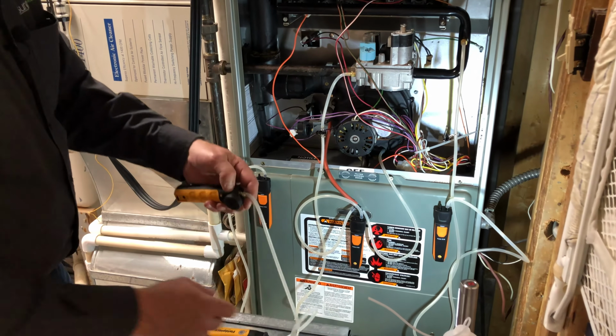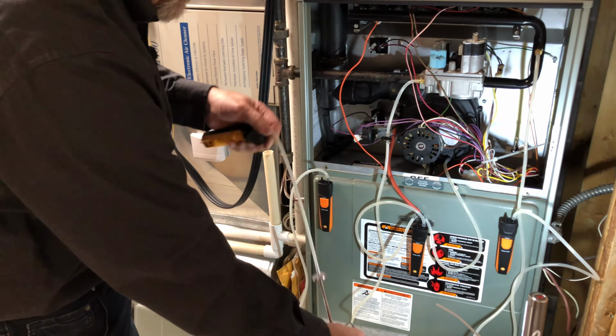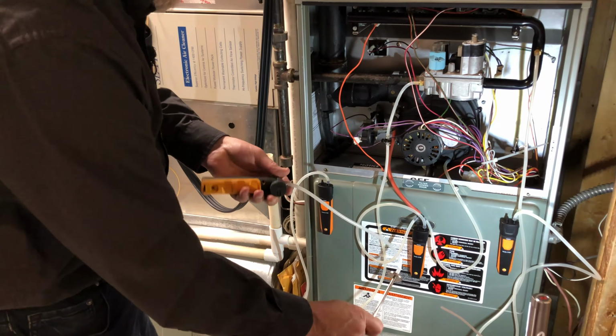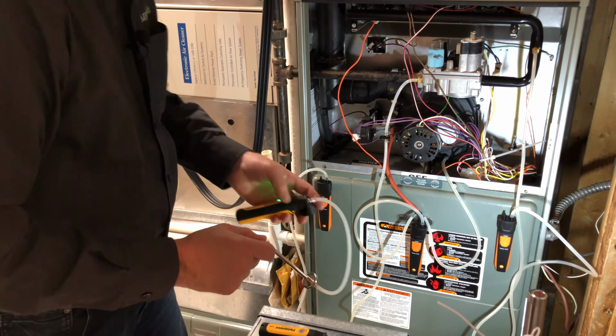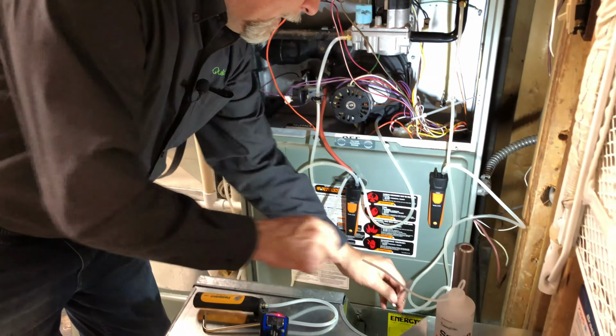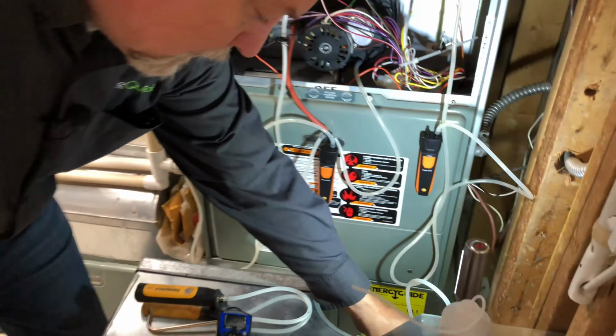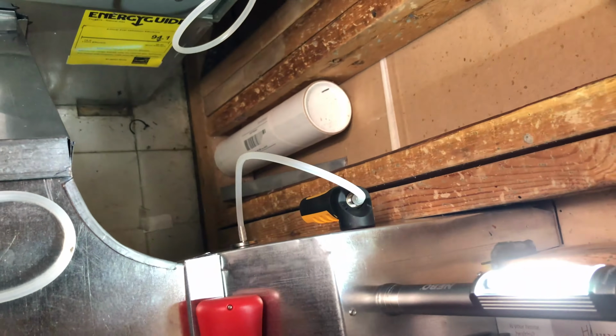I'm also going to measure my return air static pressure and supply air static pressure. So I'm going to go ahead and turn these on, and I have a hole that I drilled over here, and I bumped my CO meter. We don't have CO in the room. I just hit the little test button there with my hand.